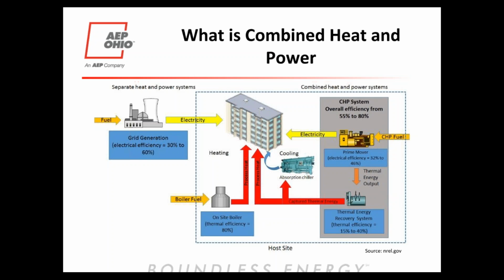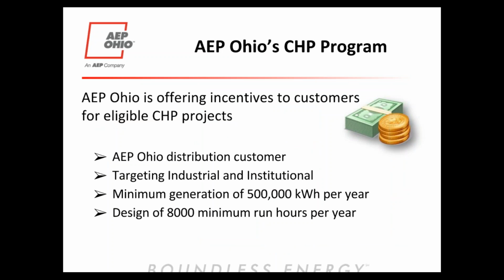It's important to note that although the CHP system may increase the amount of fuel used on site because of the additional fuel required to operate the prime mover, there are still potentially energy savings to be had by reducing demand and electric load. So you can reduce overall energy costs with the CHP system.